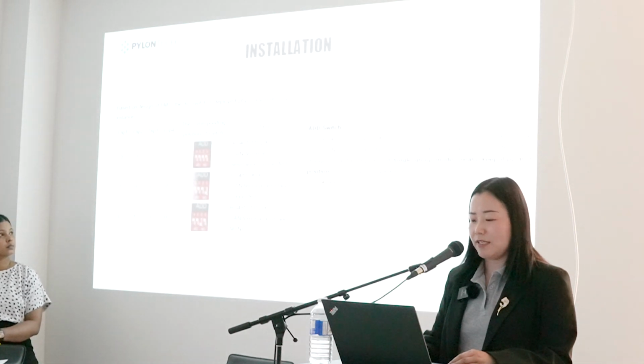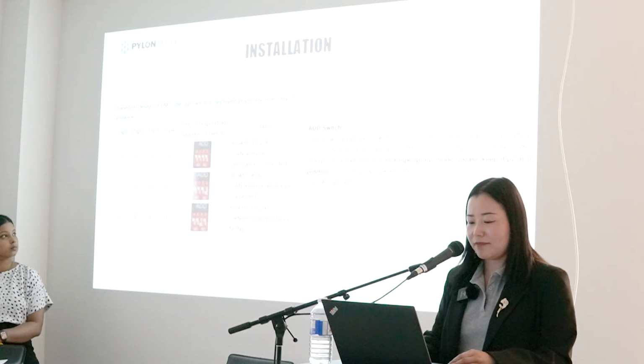For installation, we have our RS485. Here is the DIP number order, and here we give you a tip: the DIP number order is reversed. So 1000 means switch the right one. You could follow the number: upper is 0, down is 1. We only need to set the address on the master battery modules.